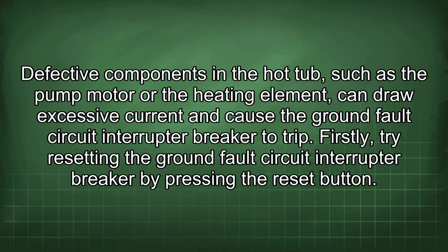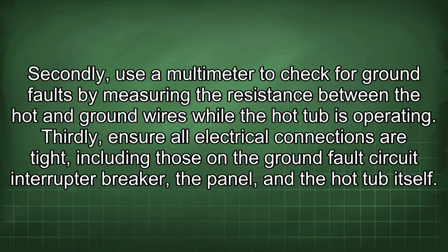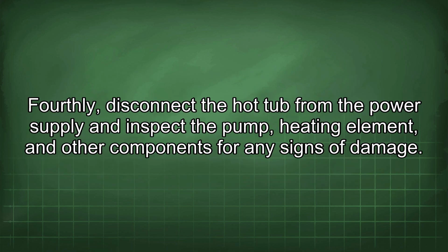Firstly, try resetting the ground fault circuit interrupter breaker by pressing the reset button. Secondly, use a multimeter to check for ground faults by measuring the resistance between the hot and ground wires while the hot tub is operating. Thirdly, ensure all electrical connections are tight, including those on the ground fault circuit interrupter breaker, the panel, and the hot tub itself. Fourthly, disconnect the hot tub from the power supply and inspect the pump, heating element, and other components for any signs of damage.